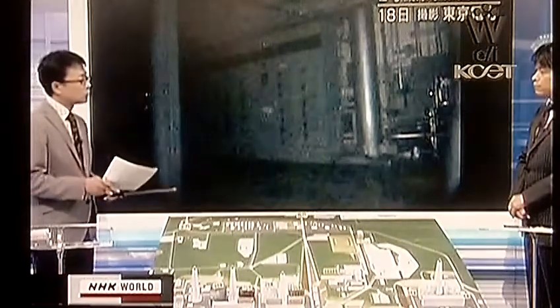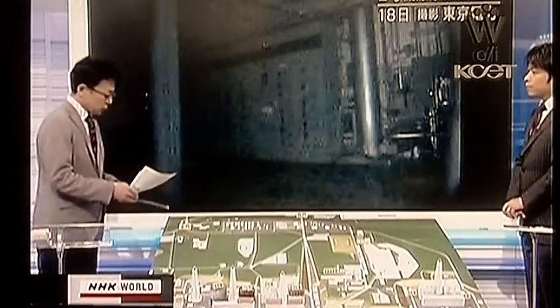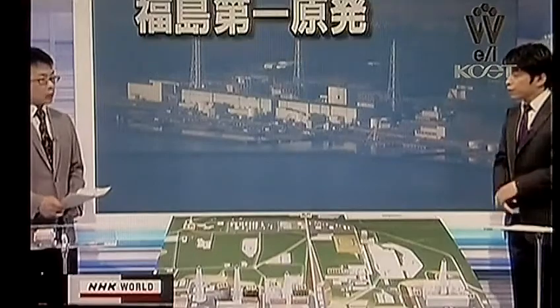The problem is unit 2. The image is not as clear as those of units 1 and 3 because the camera lens was obscured by high humidity — almost 100% — and temperature was higher than 40 degrees Celsius. The radiation level was not very high, but for workers wearing protective clothes and masks, it is so hot and humid, just like being in a sauna bath. Once they enter the area, they cannot see anything — visibility is very poor and it is impossible to work. The steam is thought to be leaking from cracks in the suppression pool, so it has to be stopped. Today, the transfer of the contaminated water in the tunnel of the number 2 reactor to the waste water treatment facility began.